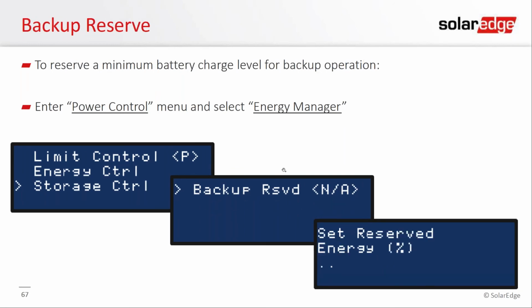And this is the reserve that you were talking about, backup reserve, how to set it up, right? Yeah, absolutely. You just go into the power control menu, energy manager, storage control, backup reserve, and then set a percentage. And is there a percentage that you recommend? Yeah, I recommend typically somewhere between 25 to 30. I generally don't recommend over 50%, because we want to use this battery for smart energy management, and I want it to generate revenue for me when I am in non-peak mode or trying to demand shave or any of these other use cases for batteries, because backup, while it is an emotional investment, is not a fiscal investment, I guess you could call it, right?